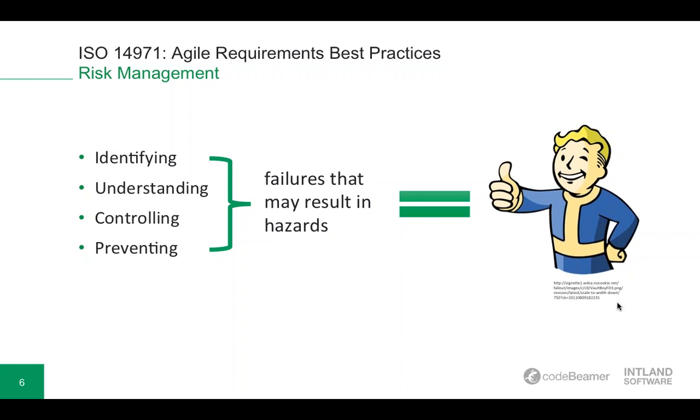By definition, risk management involves the identification, the understanding, the control, and prevention of failures that may result in hazards during the use of medical devices. Besides it being, of course, required by law, performing risk management can lead to the identification of device design problems prior to manufacturing and distribution, which eliminates costs associated with recalls. And needless to say, it can also obviously offer a measure of protection from damages from product liability claims. Also, regulatory submissions checklists used by the FDA, for example, call for inclusion of risk analysis.